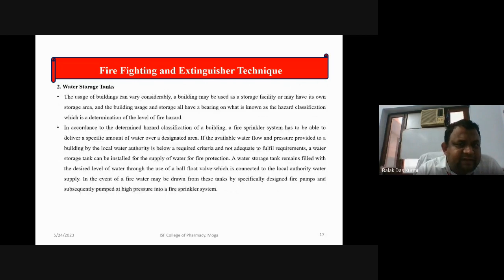Water storage tank. The use of buildings can vary considerably. A building may be used as a storage facility or may have its own storage area. The building usage and storage all have a bearing on what is known as the hazard classification, which is the determination of the level of fire hazard. In accordance with the determined hazard classification of the building, a fire sprinkler system has to be able to deliver a specific amount of water over a designated area.